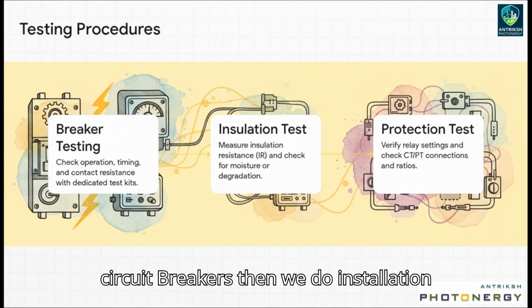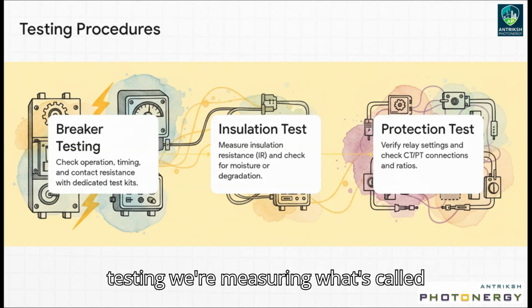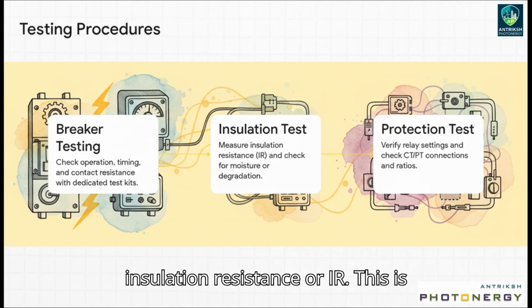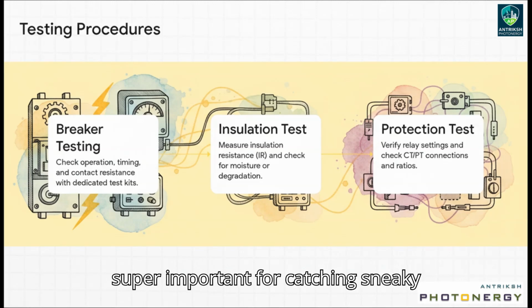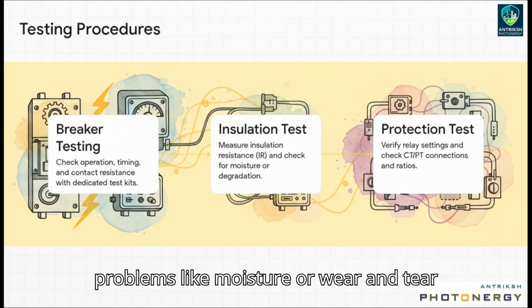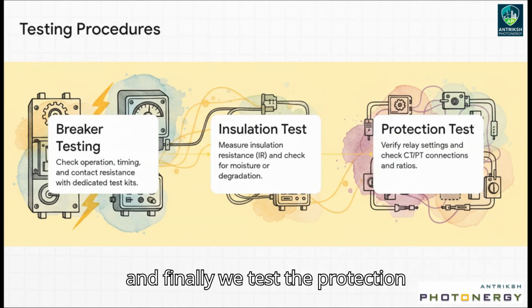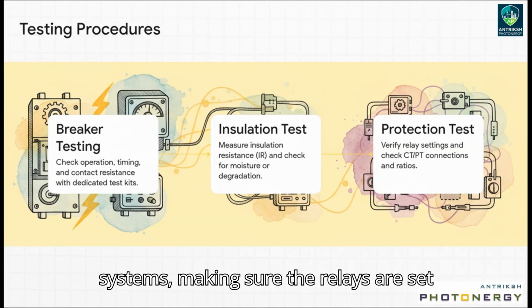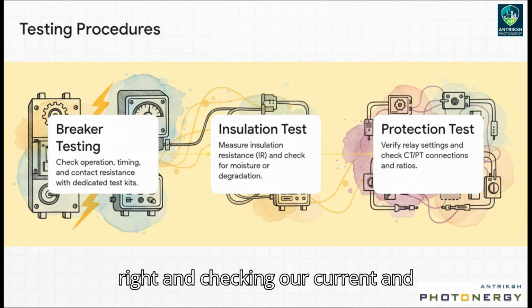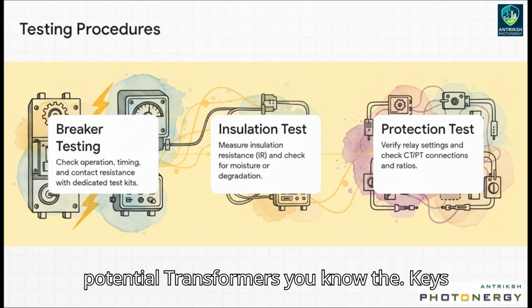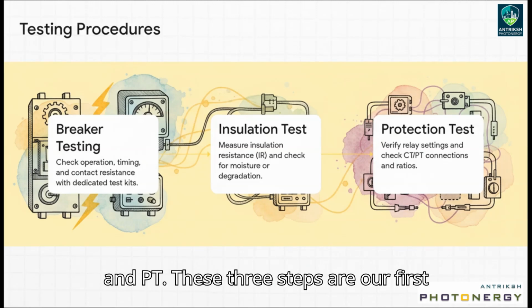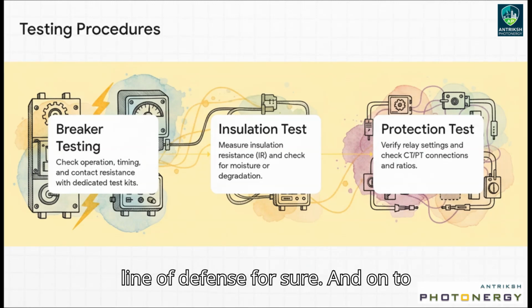First up, the circuit breakers. Then we do insulation testing, measuring insulation resistance, or IR, which is important for catching sneaky problems like moisture or wear and tear. Finally, we test the protection systems, making sure the relays are set right and checking our current and potential transformers, the CTs and PTs. These three steps are our first line of defense.